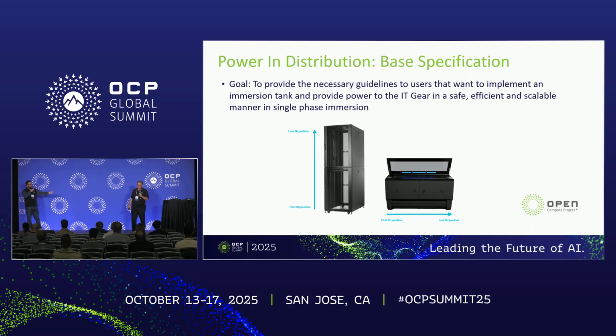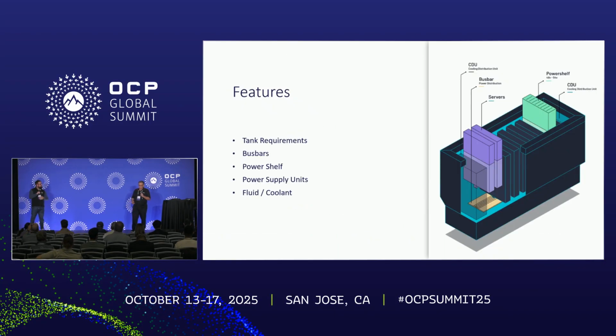These are single-phase immersion tanks. We took the similar naming convention that a vertical air rack has for data centers, and tried to replicate it into the tank by adding the busbar at the bottom, respecting the organization and polarity of the electricity — positive and negative on both sides of the busbar — replicated from left to right into the immersion tanks.